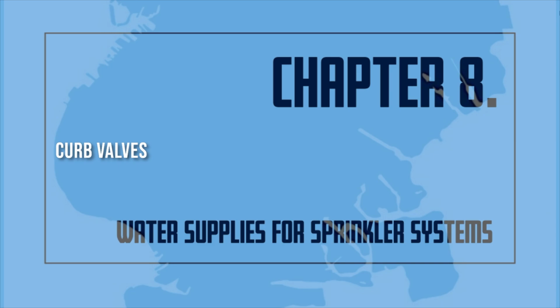Curb valves. Gate valves of the non-indicating type are provided in water distribution systems. Gate valves allow the sprinkler system to be shut off for repairs or maintenance. Such valves are normally a non-rising stem type. They are operated using a special key wrench. A valve box is located over the valve to keep dirt from the valve. The valve box also provides a convenient access point for the valve wrench to the valve nut.